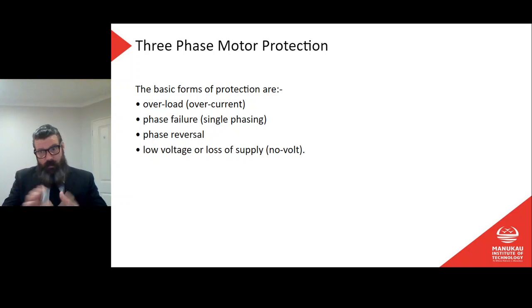Sometimes, well, it depends on the type of thing, right? Some motors need to be going forward and reverse. What's an example? A garage door opener is a great example. It's got to go up and it's got to go down. If I accidentally somehow reverse the phases on that, well, then when I push up, it's going to go down, and when I push down, it's going to go up, which is not ideal, but I'll be able to figure that out, right? I'm probably not going to cause myself too much hassle. I just have to push the other button.